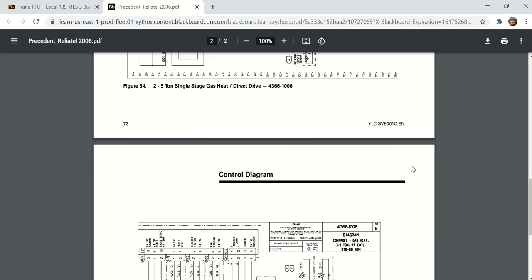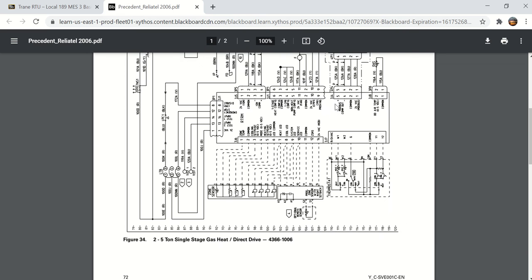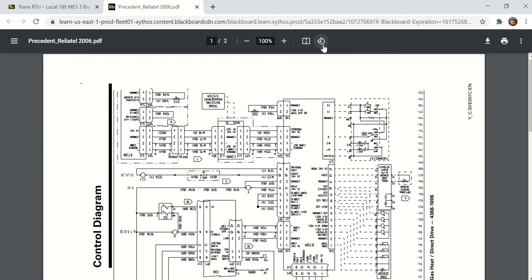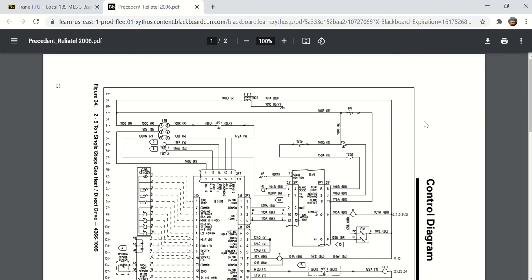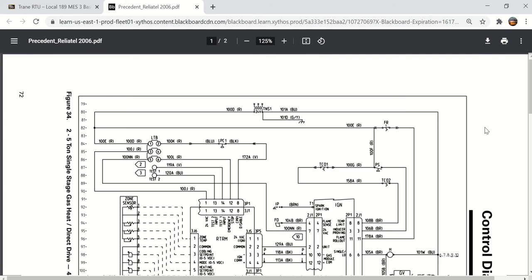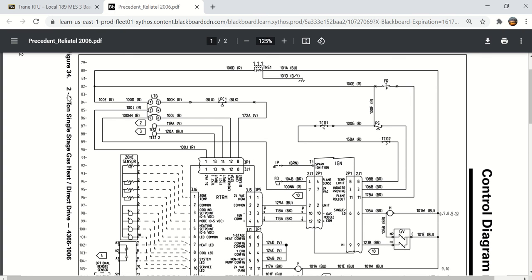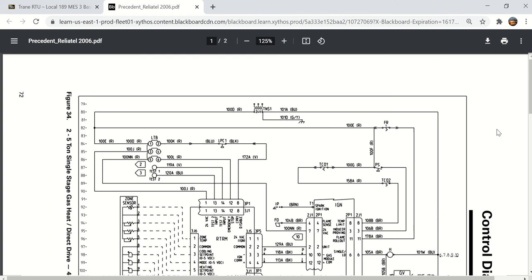Now, diagrams are turned the wrong way, so hopefully when you open these in a PDF viewer, you can rotate them the right way. So I'll zoom in here just a little bit. You can see here that this is a 2 to 5 ton single stage gas heat direct drive wiring diagram. Up here is the control transformer, 24 volt output. Here is the wire number 101D. It's a green and yellow wire that goes to ground. So they do ground one side of the transformer. Here's the power coming off the other side of the transformer.